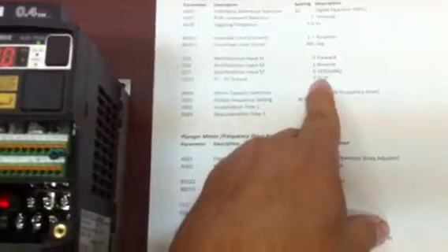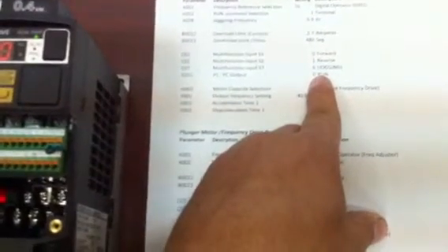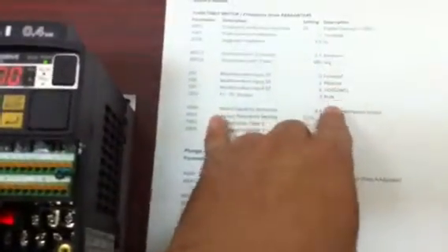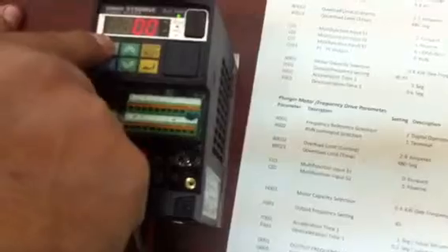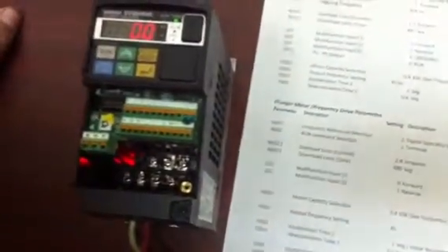That's wrong, so it's gotta be in C0. So when it's gonna receive a signal on the terminal, it's gonna go and do run on C021 as we define over here, terminal run. So it's very important to define these settings, because if they are not, the PLC is gonna be sending signals to these terminals, but the controller is not gonna work, or you're gonna wait for someone to push this button, which is not what we want for defining the running.